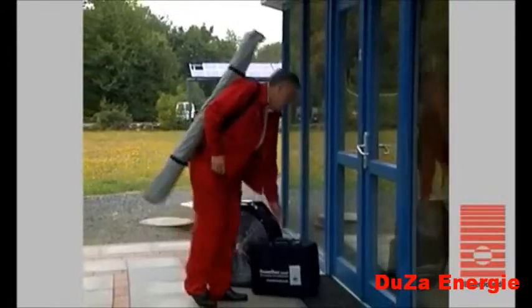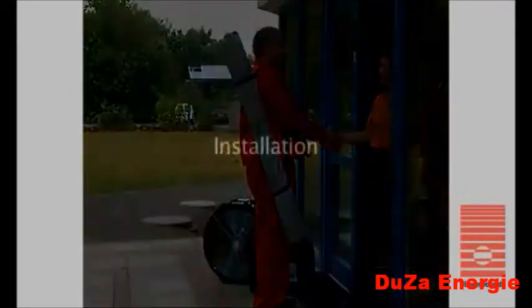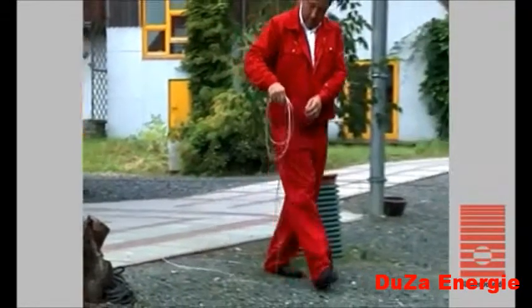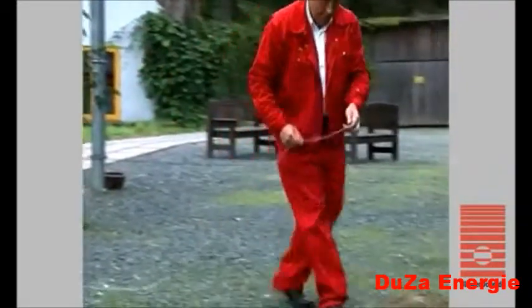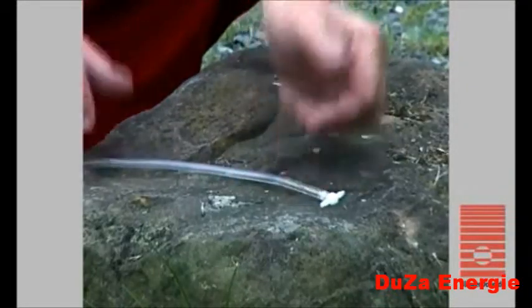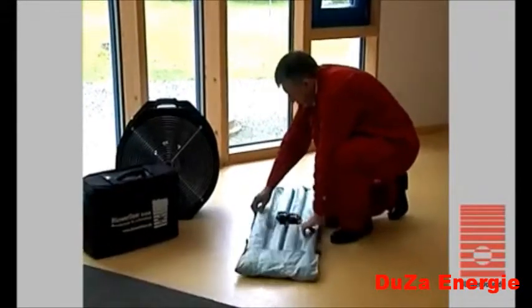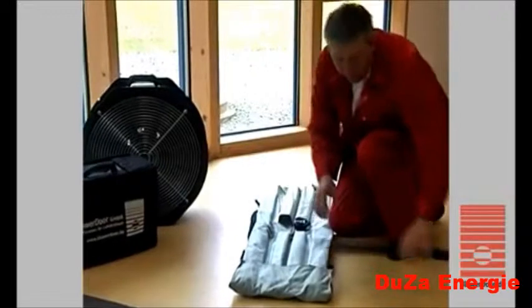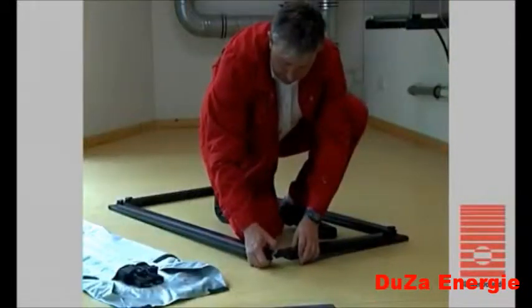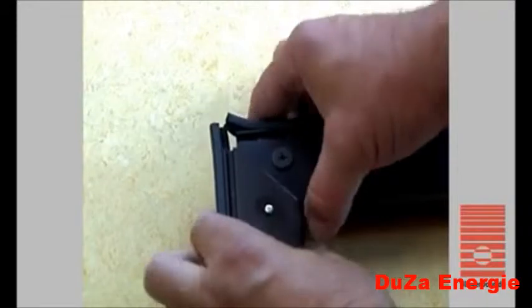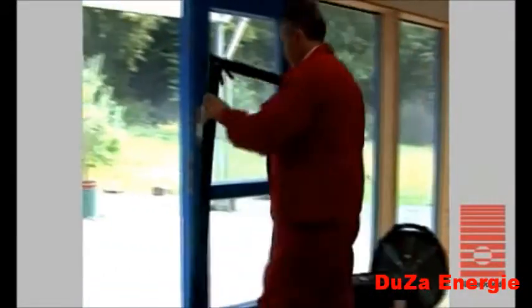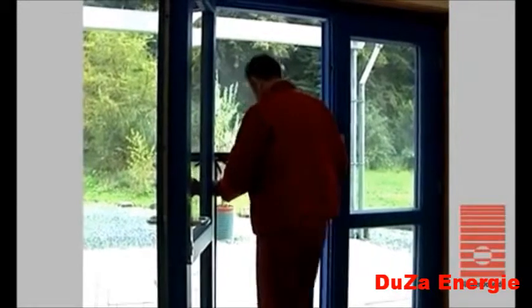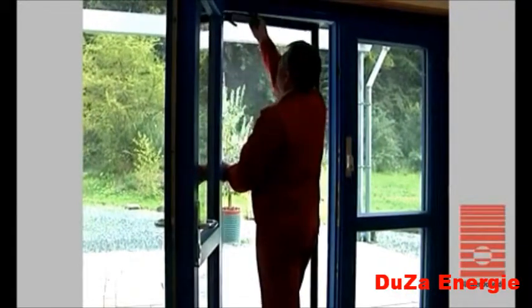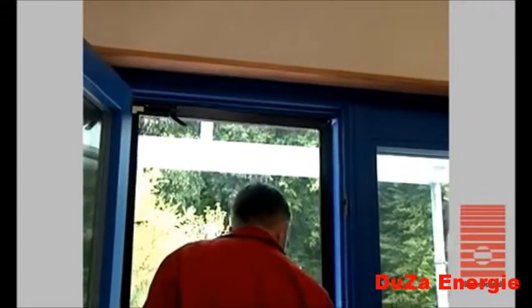The blower door is installed in an exterior doorway on the ground floor. First, the clear tubing used to measure the outside pressure is placed down. The aluminium frame is easily assembled by connecting the vertical and horizontal frame pieces. The frame is adjusted to roughly fit the door jamb. At first, a narrow gap should be left between door jamb and blower door frame. The frame pieces are tightened with the knobs.